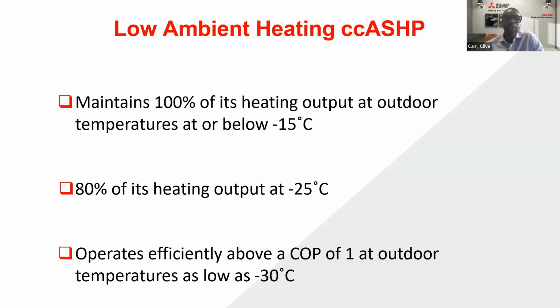When we look at the reasons behind that, Canada is very cold. We see the heating output and the efficiencies of the heat pump at those temperatures, but we don't see them at the cold point. So those two points represent operation of heat pump systems in regions south of Canada, HSPF region 4. Region 4s are milder. Areas in Canada considered region 4 might be Vancouver and Victoria because the climate is milder there. But for the rest of the country, we are in region 5, which is a colder climatic condition. Our average temperatures in these regions sit more around minus 15, and the average of the cold point sits more around minus 25.